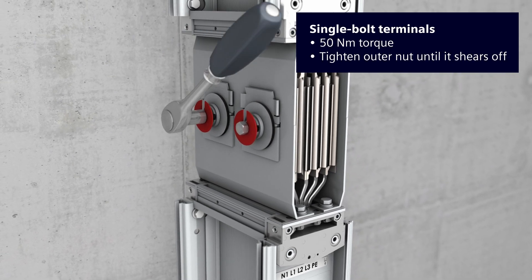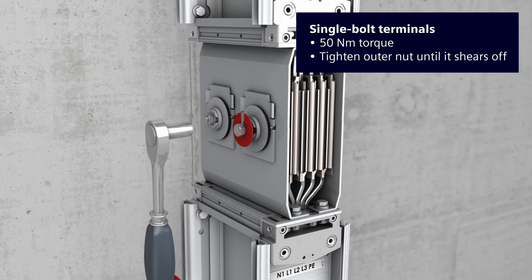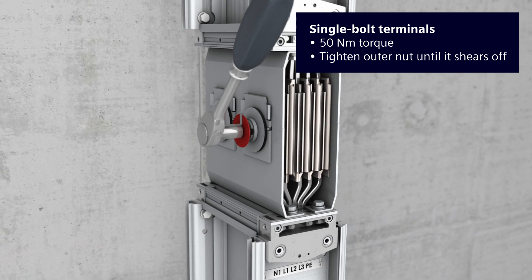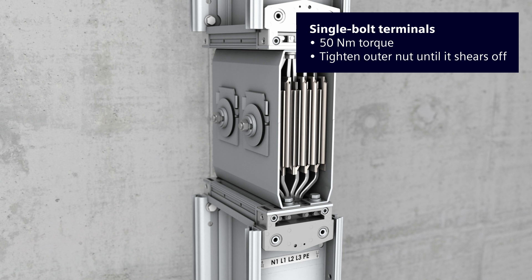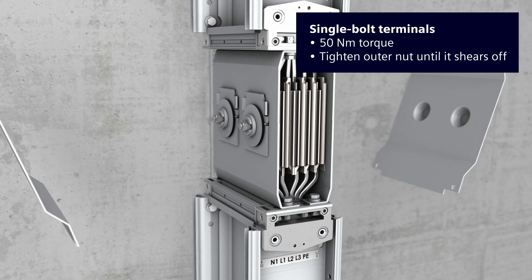During initial installation, the two single bolt terminals can also be tightened without a torque key. Tighten the outer part of the double-headed nut until shearing off. That will represent a torque of 50 Newton meters.